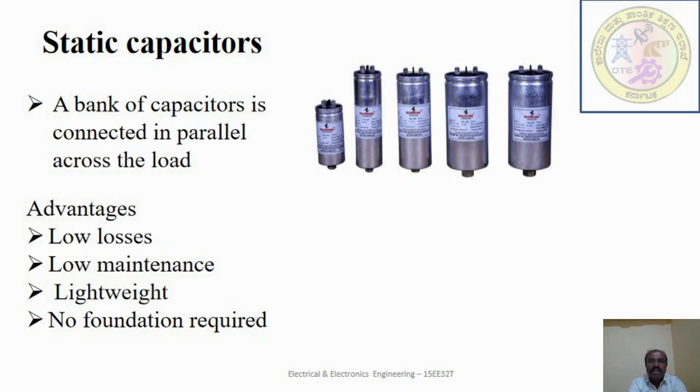The power factor can be improved by connecting the capacitor in parallel with the equipment operating at lagging power factor. The capacitor, which is generally known as static because it does not have any moving part, draws a leading current and partly or completely neutralizes the lagging reactive component of the load current. If the lagging reactive component is completely neutralized, there will be a rise in power factor of the load.